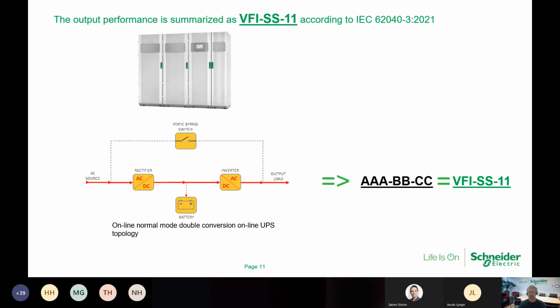A summary of the test and the standard's definition. The UPS is double conversion, unlike a UPS operating in normal mode, and can regulate both output voltage and frequency. So according to the standard, the classification coding AAA is voltage and frequency independent, so VFI. The sine wave inverter delivers power to the load in both normal and stored energy modes, so the standard classification coding BB is SS. The inverter continuously supplies power to the load during power failure, and because the inverter handles step loads well, the standard classifies the dynamic output performance as 1-1. Then the complete output performance is VFI, SS, and 1-1 according to the standard, the -3 from 2021.